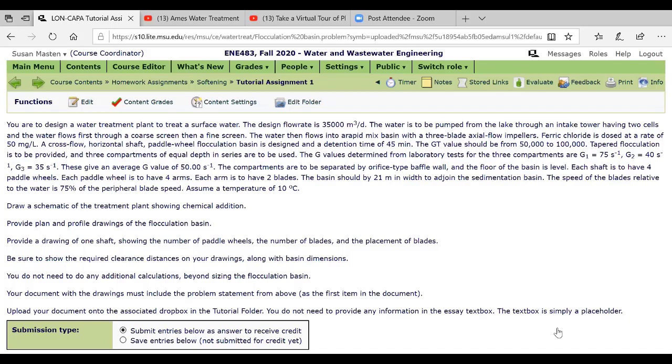So I've told you about the rapid mix ferric chloride and told you the dose. I give you the cross sectional, so you've got a cross flow horizontal shaft paddle wheel basin and it has a detention time, give you the g value. Tapered flocculation is provided and you've got three compartments of equal depth in series. I give you the g values and those will vary with the student, and that gives in this case an average g value of 50 inverse seconds.